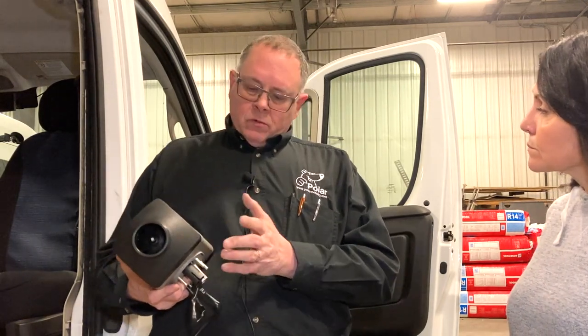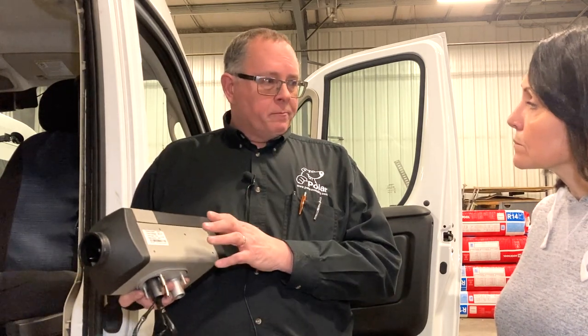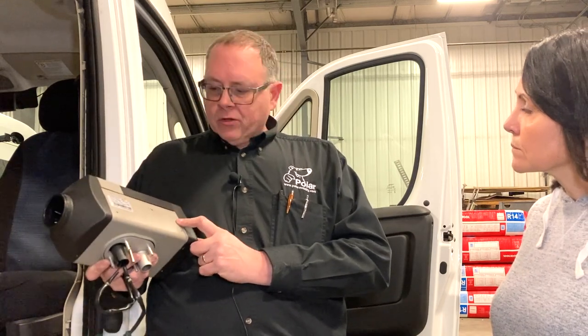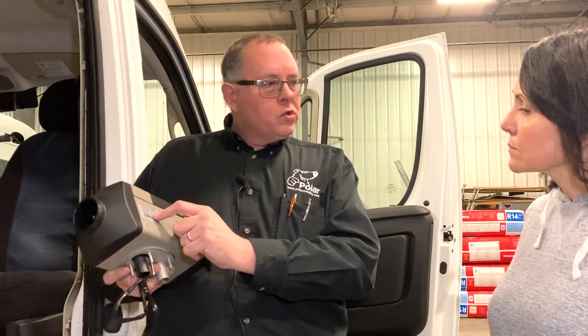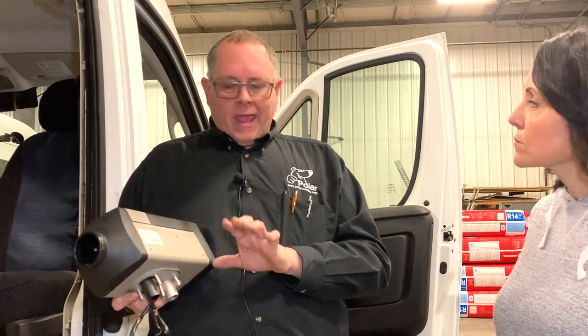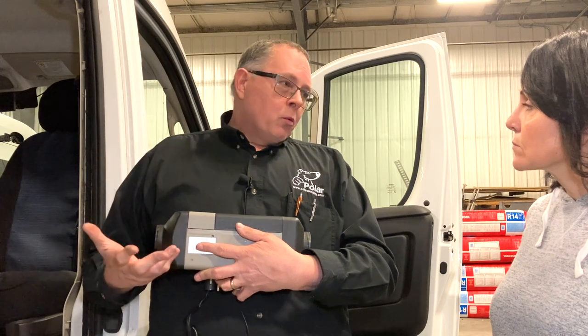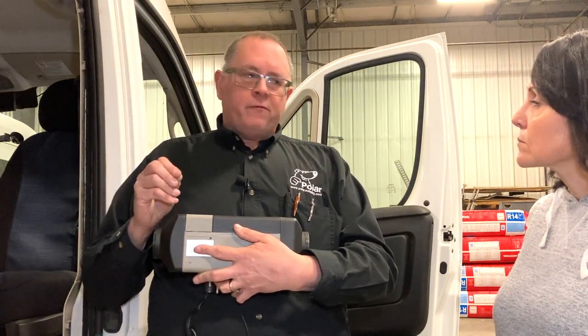If they're running this on the house battery, they need to make sure they're charging it the next day. Most heaters are similar in electrical power draw, pulling 9 to 10 amps for about 90 seconds on initial startup. Once the sensor in the flame detector detects a flame burning, it drops down to typically about 1.8 amps. Once the heater is up to temperature and just cycling to maintain, a heater I know would draw about 0.8 of an amp, which is very, very low.